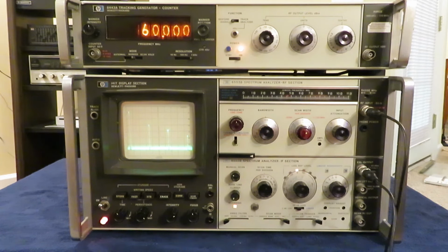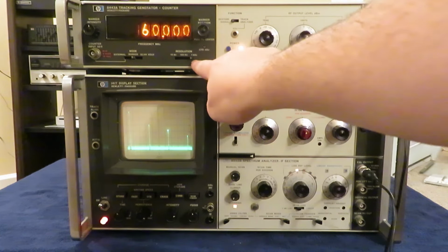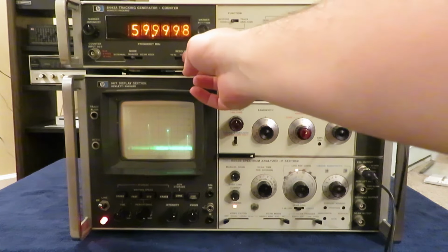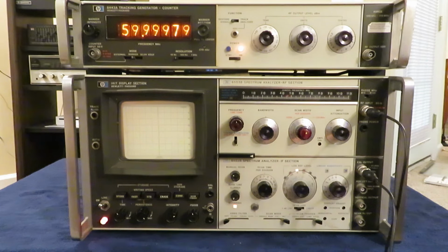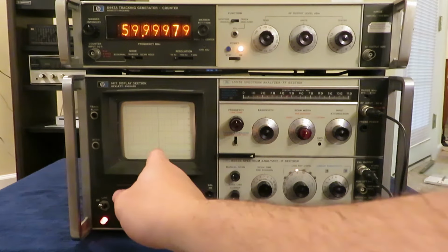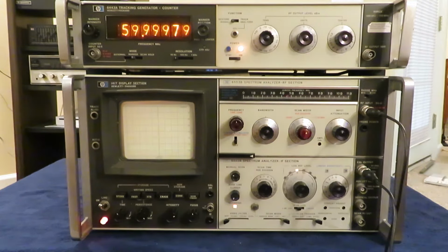And you can also adjust the gate time of the counter to get more resolution. So right now it's set to 1 kilohertz. You can also drop it to 100 hertz and even 10 hertz, but you can see that it actually will pause the sweep midway through and dwell on that peak for a little bit longer, so it makes the display flicker. Just something to keep in mind if you are using one of these. So it's not ideal for doing fast sweeps like this.